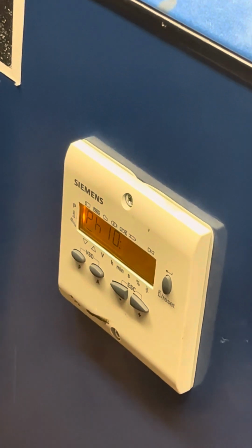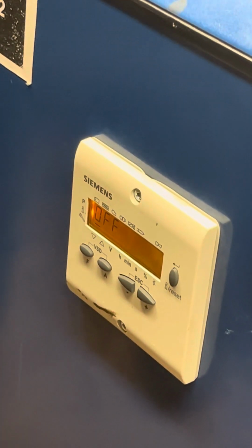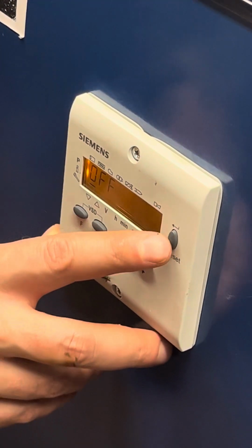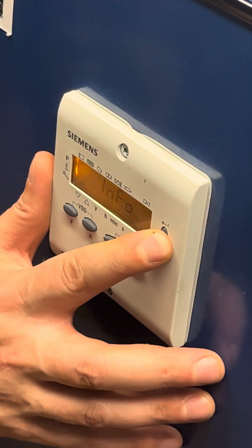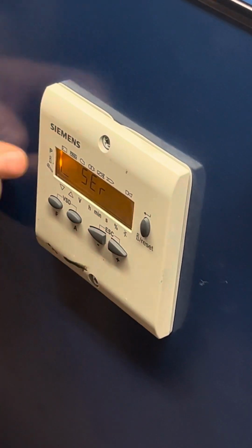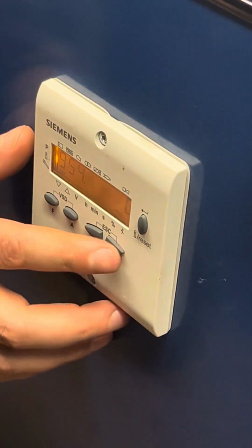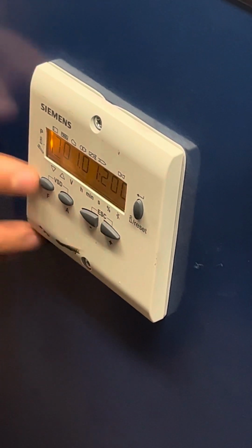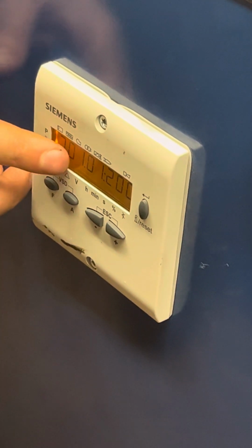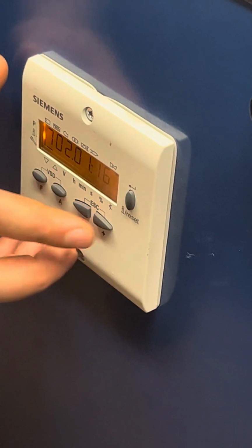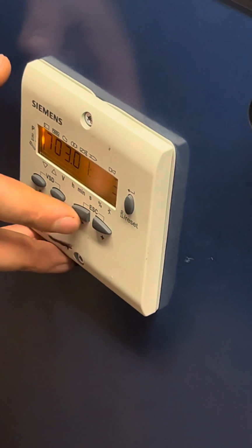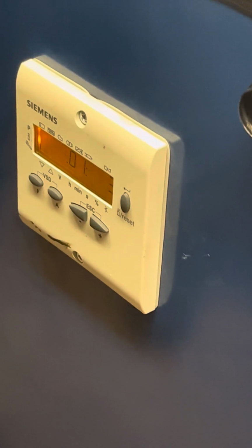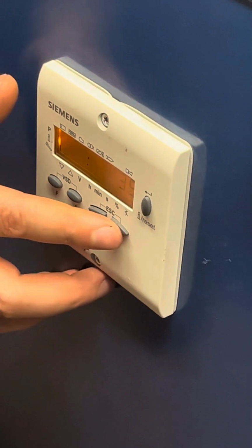Now, if you wanted to check your history to go back and see what your previous lockouts are, you're going to hold your reset button, and then the screen is going to change. It's going to start cycling through info and then service, SEr. And then you're going to scroll until you get to the 700 numbers. So 701, 702, 703. That's logging all the lockouts. I think this will say the last 5. So you can go from 701 to 705 and retrieve the diagnostic codes.